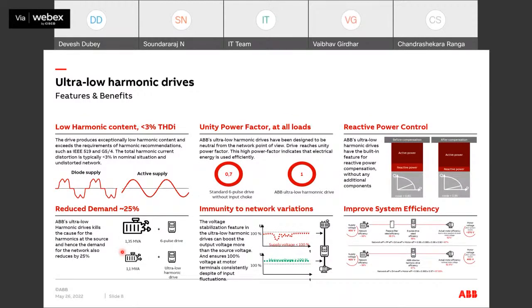Moving forward, what are the benefits and value propositions which an end customer from the cement plant is going to get? First point is the low harmonic content. As I told, it will be less than 3%, which meets the IEEE 519 norms, or is better than that. You have a unity power factor at all loads. A standard 6-pulse drive without input choke will have a power factor of 0.7 or 0.6, while with the low harmonic drive or active front-end drive, we will have unity power factor.